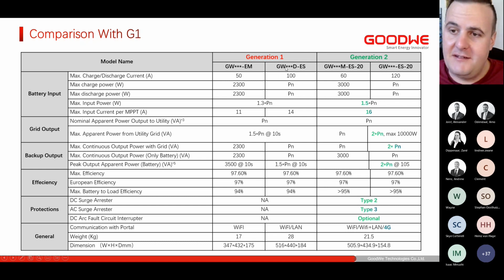Then we look at the ES. So the old ES 5048 had a maximum discharge current of 100 amps. The new one is 120 amps. Then the battery input. We'll see the maximum power it can take up to 1.5 times. That's for the DC input. And then the max input current per MPPT is now 16 amps instead of the old 11. This was upgraded to 14 at the end of the ES, so it might be a bit confusing, but it is now 16 amps, so it gives us a much wider range for modules.